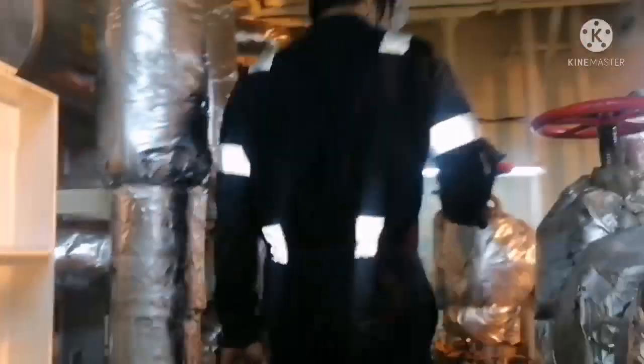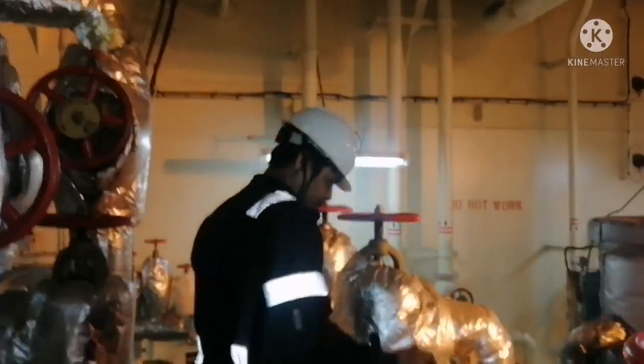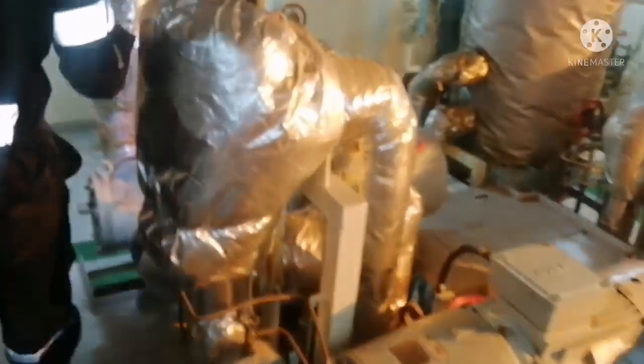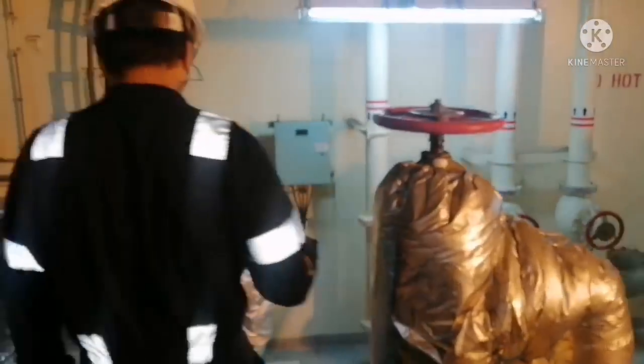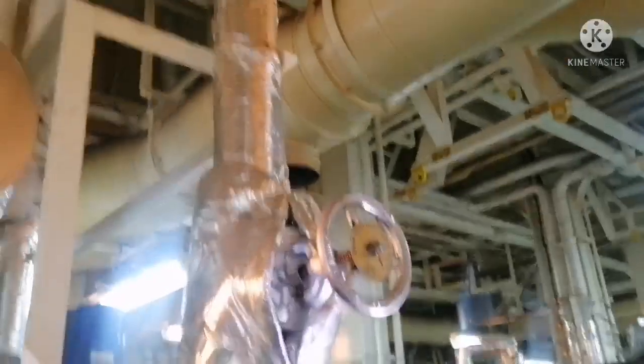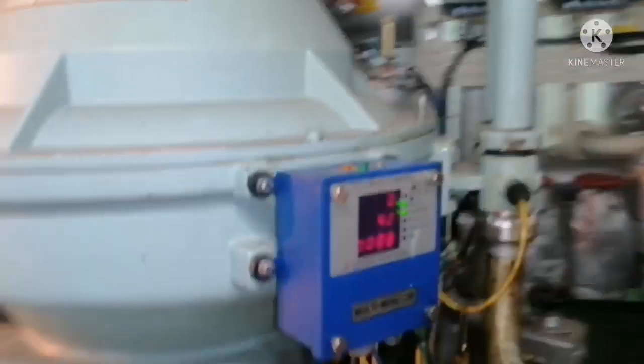You just check for the purifier parameters. Just check for any leakages, any steam leakage, any fuel oil leakage, or any kind of abnormalities, any drop in pressure, any abnormal noise in motors, any abnormal noise in purifiers and everything, you have to check. Here I can find small leakages, so this is not a big issue, but we have to attend it. So we will tighten the gland so that there won't be any leakage. So again, all the pumps you just check for the pressures, there is no leakage, no vibration, no abnormalities found.